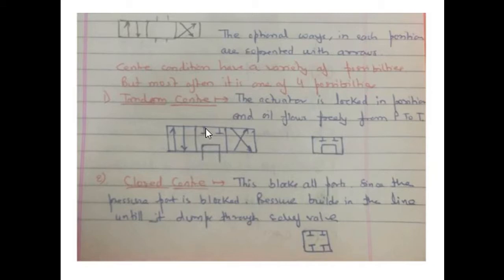And the actuator, whatever it is, it may be a ram or the vanes of a steering gear, it will be locked in the same position. Number two is closed center. This blocks all the ports. Since the pressure port is blocked, pressure builds in the line until it dumps through the relief valve.